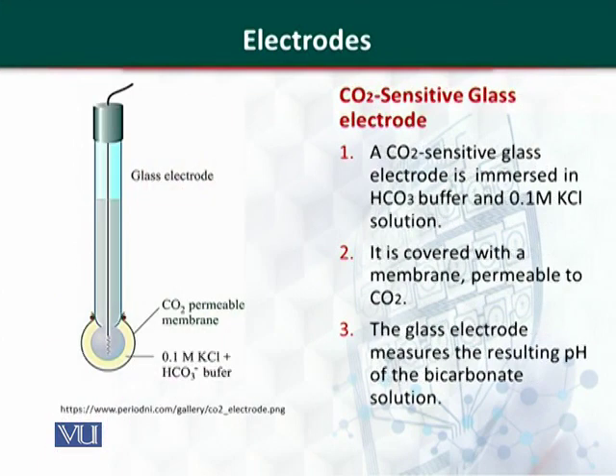The first type of electrode we are going to discuss is the carbon dioxide-sensitive glass electrode. This electrode is used to determine the amount of carbon dioxide in the blood. It is a glass electrode that uses a gas permeable membrane, which keeps the electrode solution separate from the biological sample.